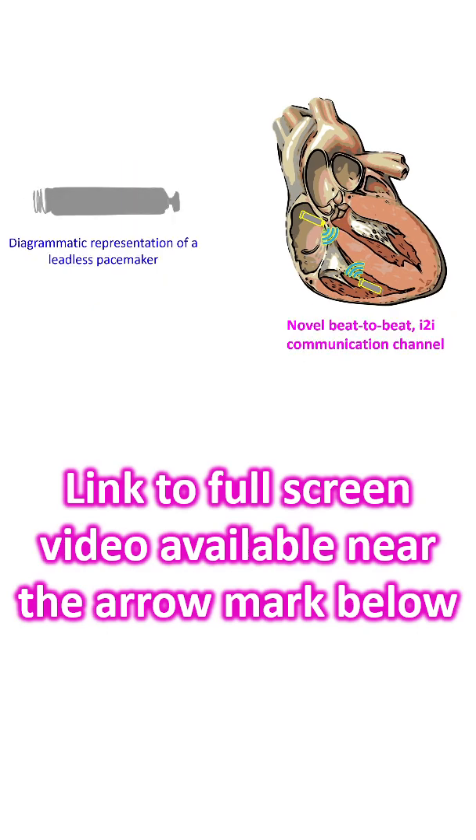The leadless dual chamber pacemaker system was designed for AV synchronous pacing using wireless beat-to-beat implant-to-implant communication between distinct atrial and ventricular leadless pacemakers. Though AV synchrony can be definitively verified only by manual ECG evaluation, i2i success rates can be readily obtained by interrogation of the devices using a programmer, and can be used as a surrogate for AV synchrony estimation.